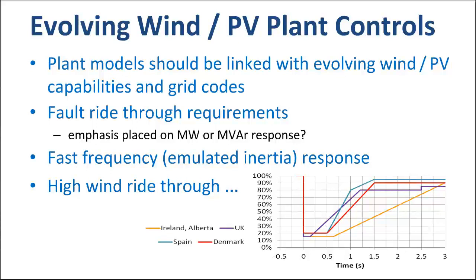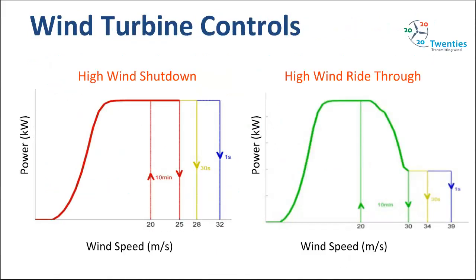It's worth playing around with these models so that they match your particular system, so that they match grid code requirements in your particular system. So for example, you might want to look at the fault ride-through requirements. Typically these models do not include an emulated inertia capability, so you might want to include something like that. And they typically don't include things such as high wind ride-through. So there may be additional capabilities that you might want to include.